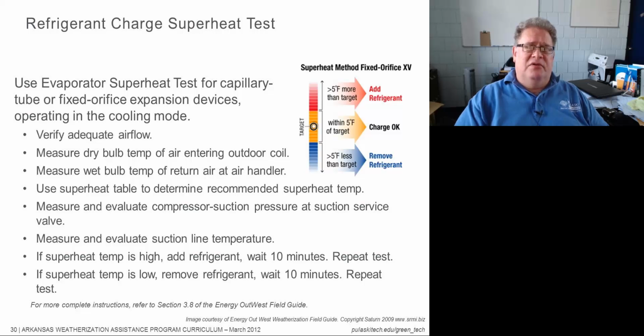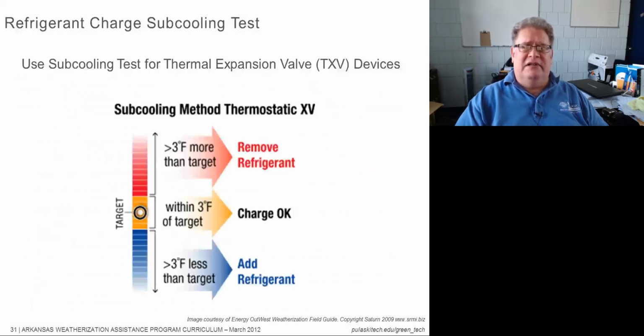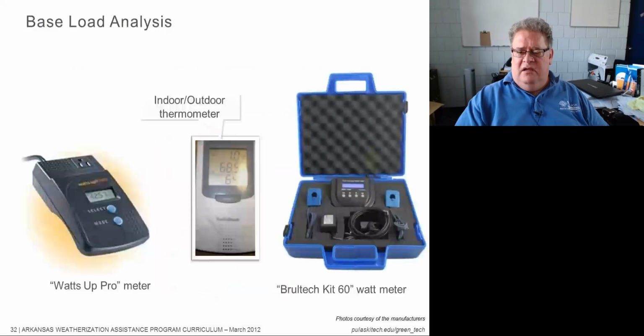For the refrigerant subcooling test, you're going to use a subcooling test for thermal expansion valves. And if you're more than 3 degrees above your target, or 3 degrees below your target, you're either going to remove or add refrigerant to the charge. Okay. Base loads. Base loads are really interesting. These are the things that use electricity that we don't otherwise use for heating or cooling. So this is something that's happening all the time. Things like water heaters and refrigerators.